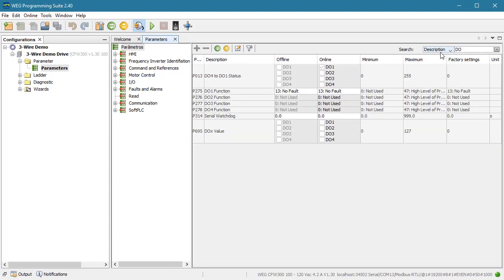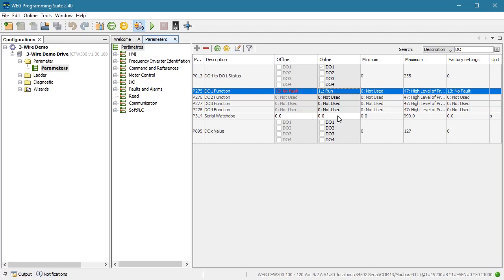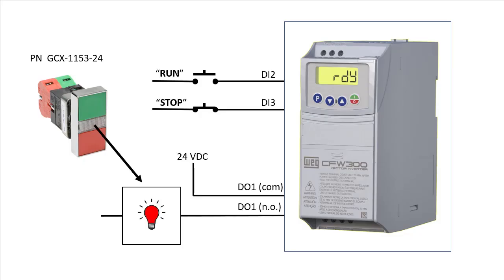I'll just search on digital output and change DO1's function to run. That just indicates the run status of the drive. I wired the drive's digital relay output normally open contact like this to the indicator in the switch.